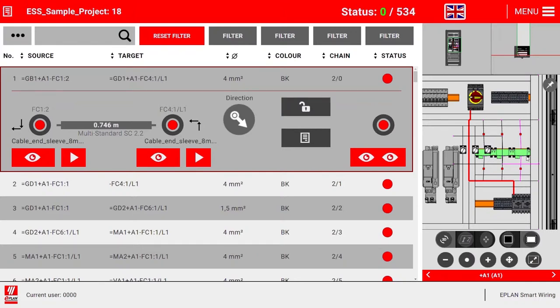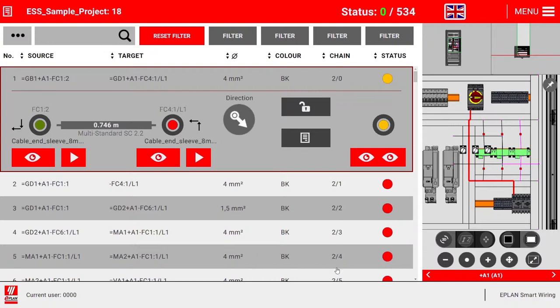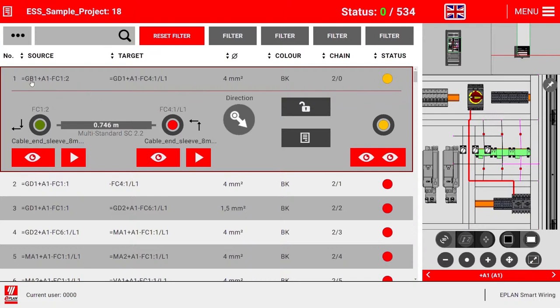Let's see what you can do. Click on the first wire. We get a little green tick to say I've started the first wire, it is now in place. You can see GB1A1 FC12. There's a little chain section here. This is part of the chain - these wires are all electrically connected together. This functionality allows you to have a quick look at GB1A1 FC12 and see if that's actually connected anywhere else in this chain. It makes a difference to see that you need to check that chain to make sure it goes to the right place.